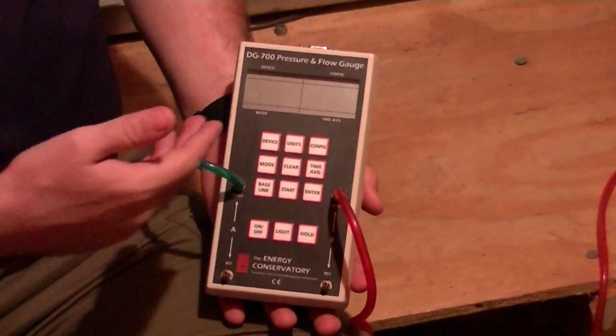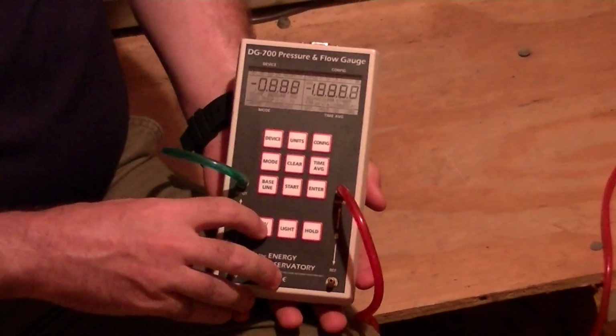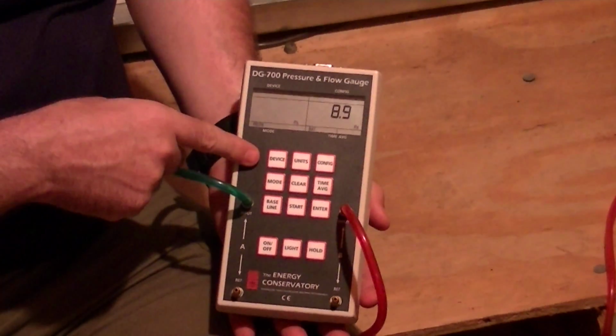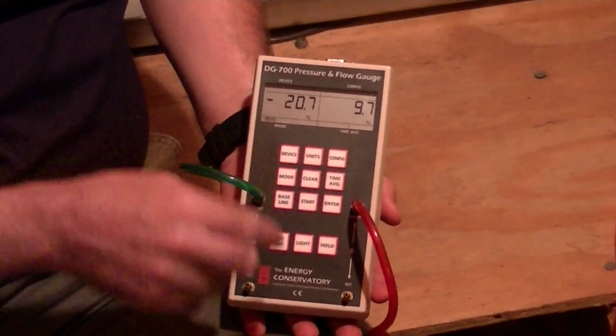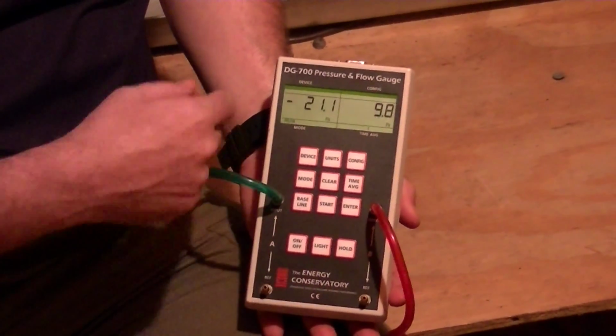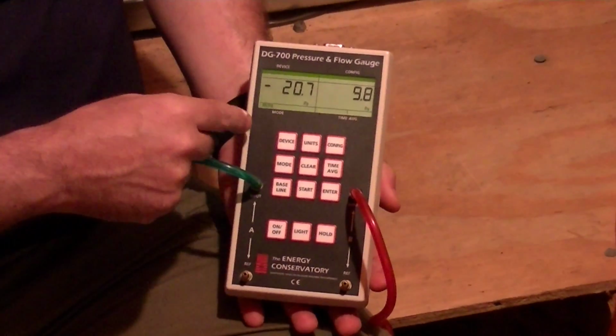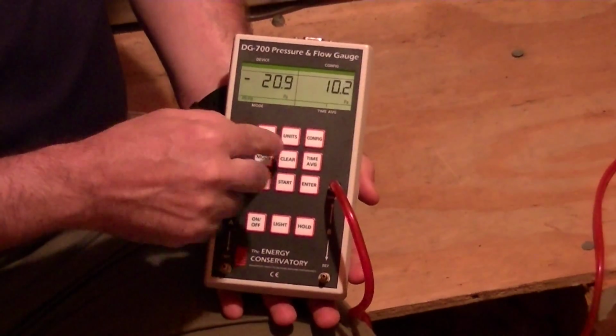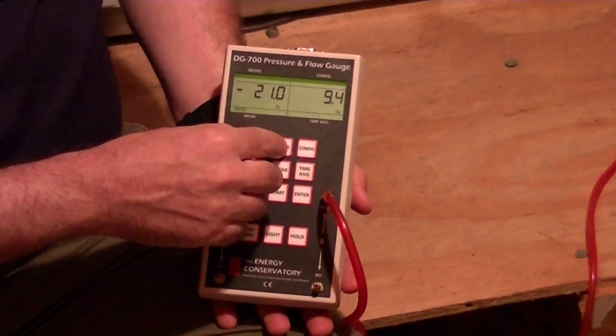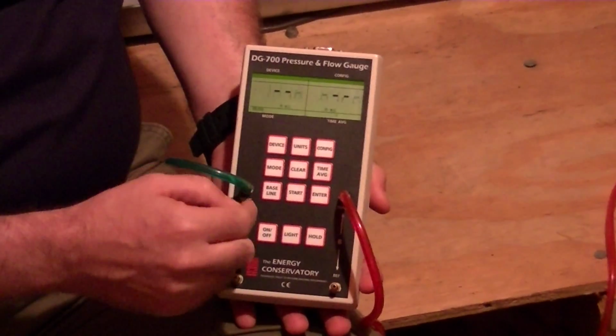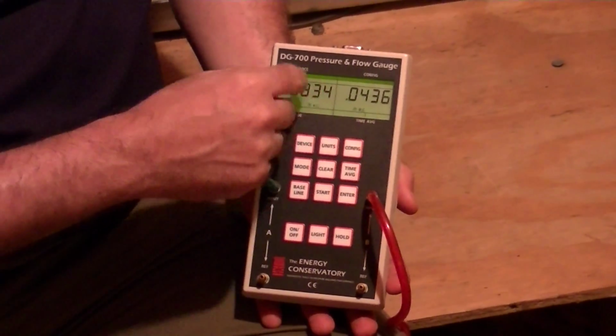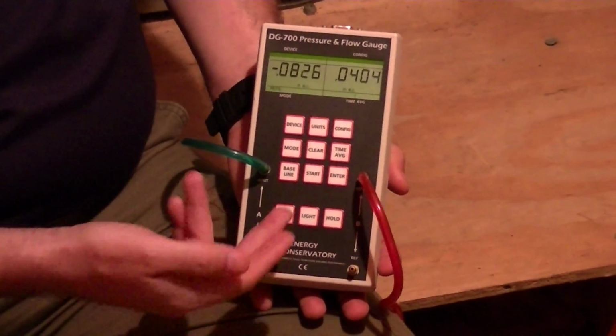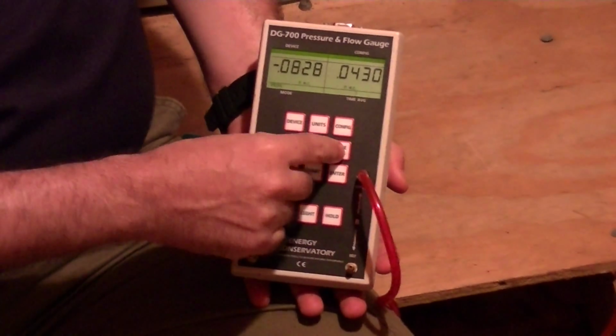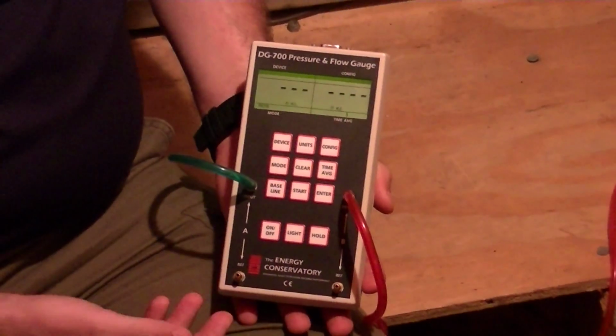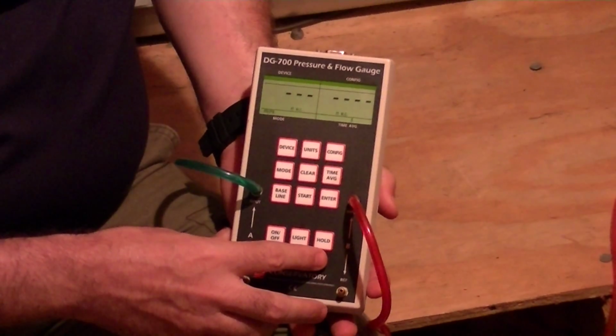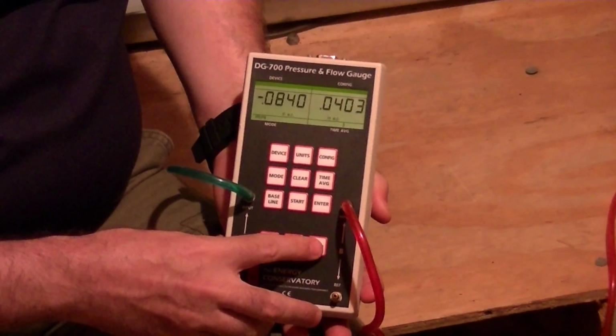Now that we have the gauge connected, we turn it on. We leave the device alone, so it's going to be reading pressure up here. We press the light button so that it backlights the gauge readings for us. You'll notice that it's bouncing around. It's in pressure mode. We change it from reading pascals to reading inches of water column by pressing the units button. You'll notice again that it's bouncing around, and that's because this gauge is taking a reading every second. So if we press the time average button, it's going to take a reading every 5 seconds. And we just wait and see what magic happens.